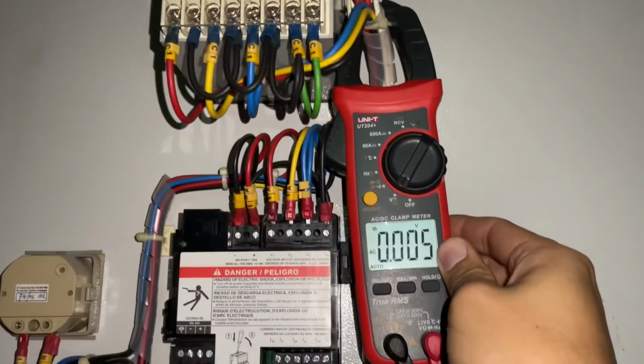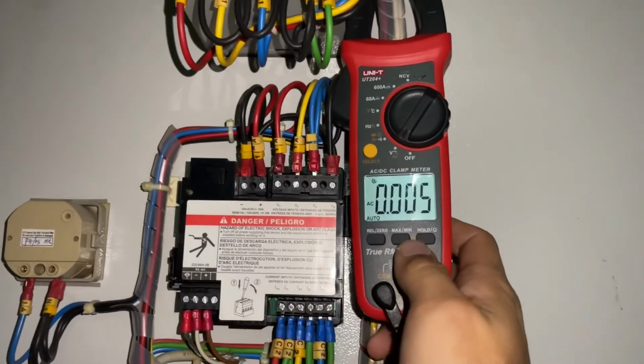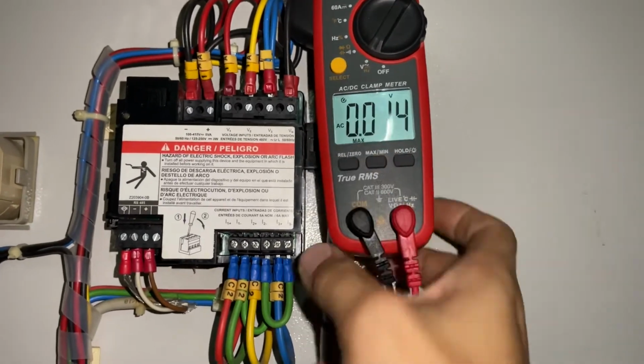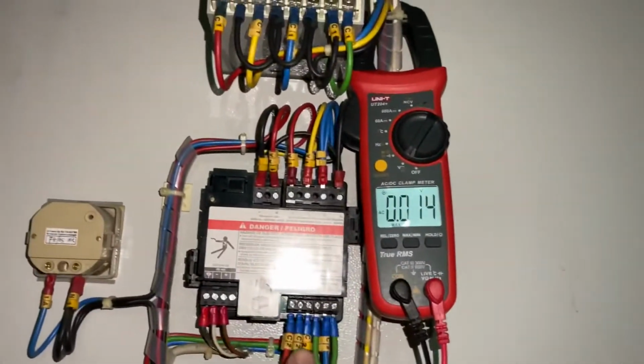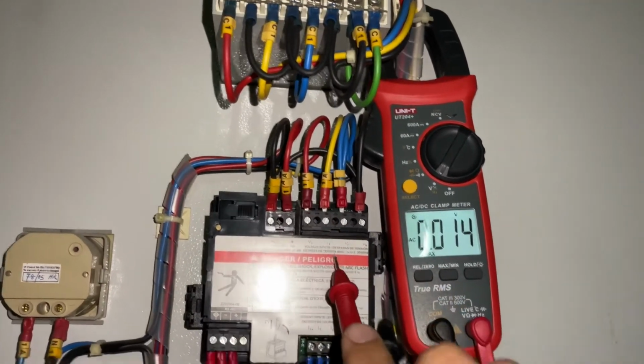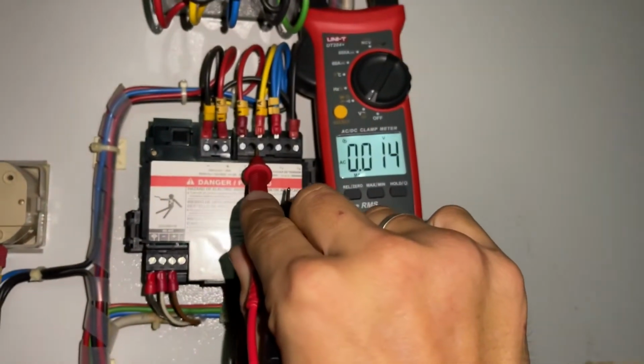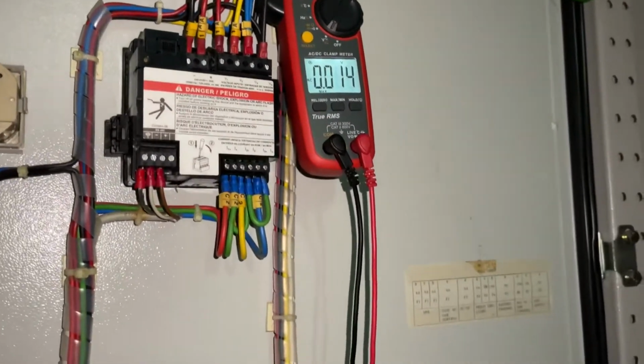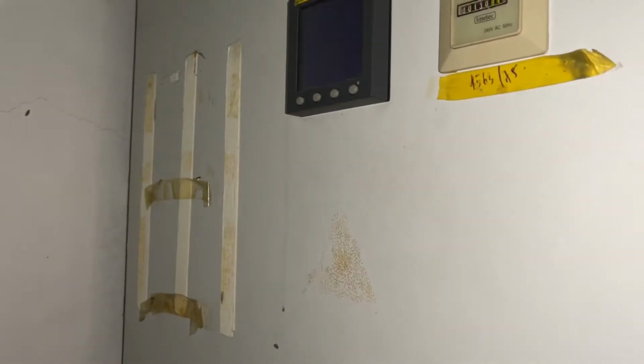So we are going to use the UNI-T Clampmeter to check the maximum voltage fluctuation during this genset startup. Okay. Alright, now here we have the Clampmeter in ready position, put to the voltmeter, and then here select maximum functions. Okay, I'm going to put my probe into the voltage terminal just to measure the maximum voltage fluctuation. So I'm going to put the test mode. Okay.